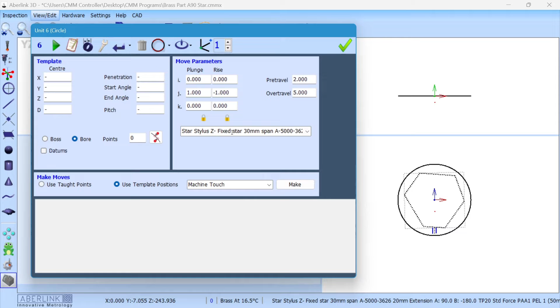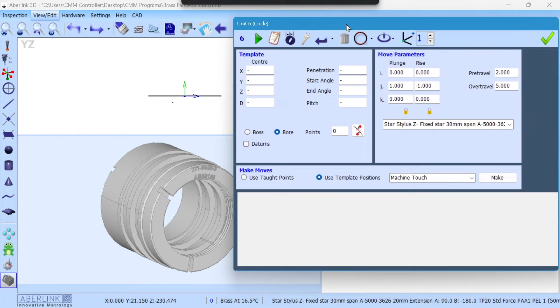So because we've got these set correctly, we don't want them to change. We'll use the padlocks and that will lock the vectors so that they can't change even though we are going to start taking points with the star probe offsets. So now we've got that done, we can switch over to the CAD and start taking a measurement.